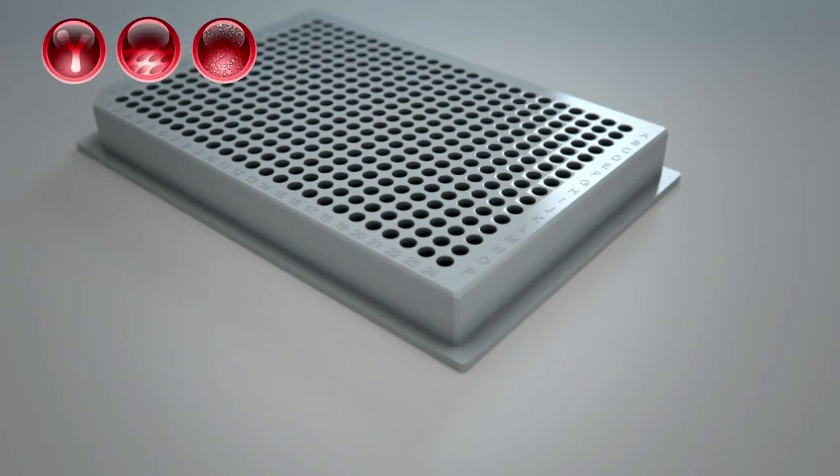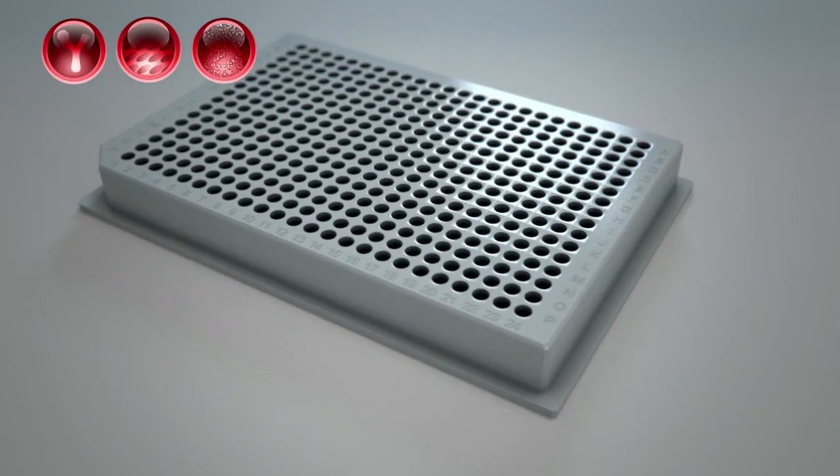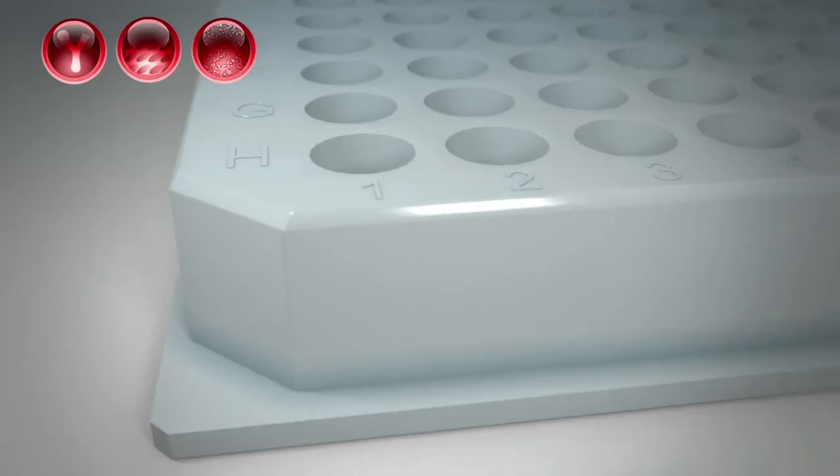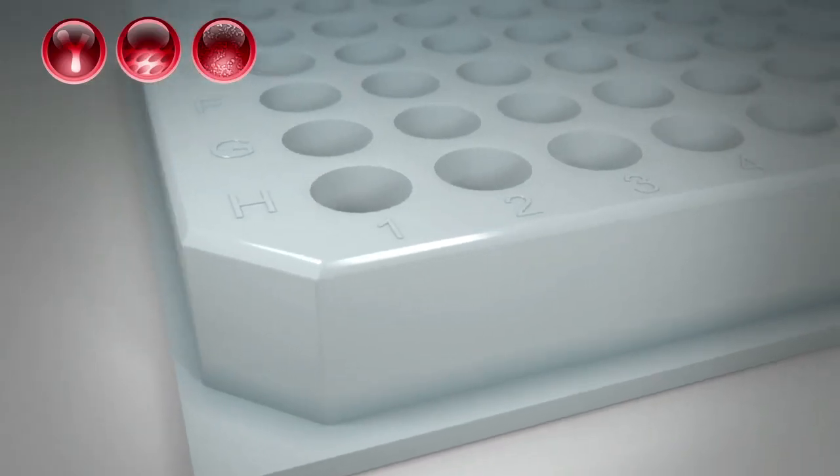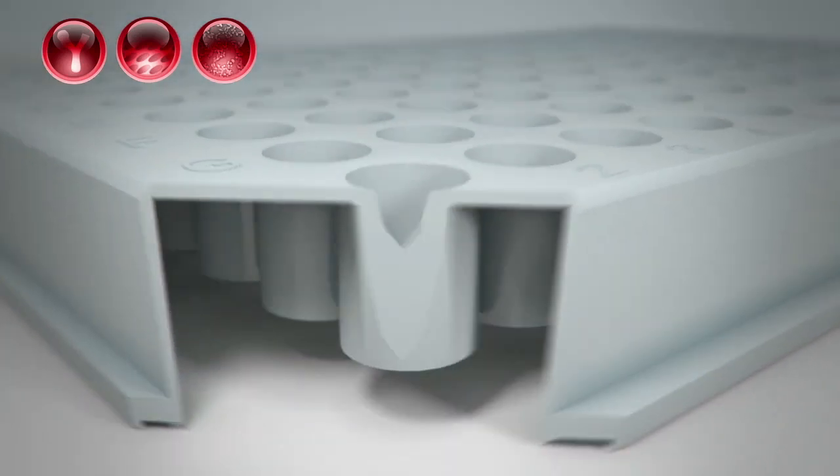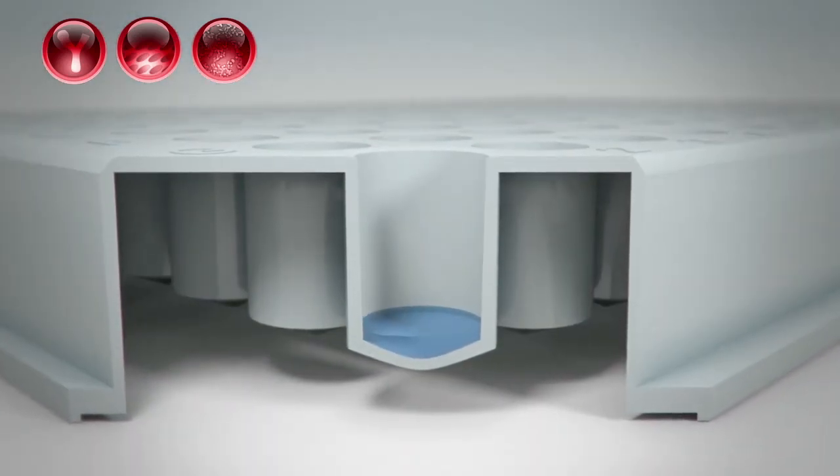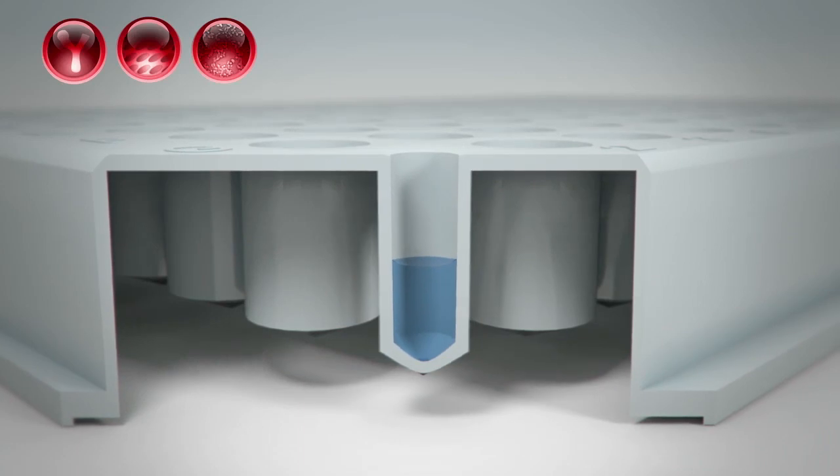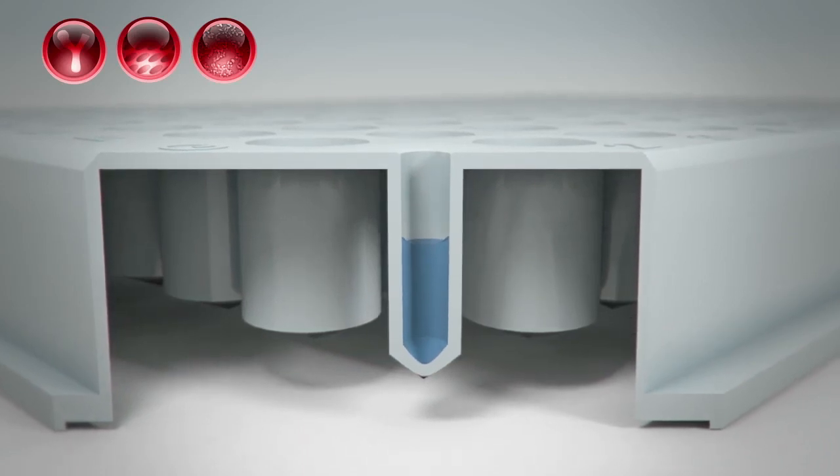Drying times, depending on the desired level of dryness, are as little as 5 seconds. Not only does conventional aspiration take more time for high-density plates, the residual volume also becomes a bigger problem as the wells get smaller.